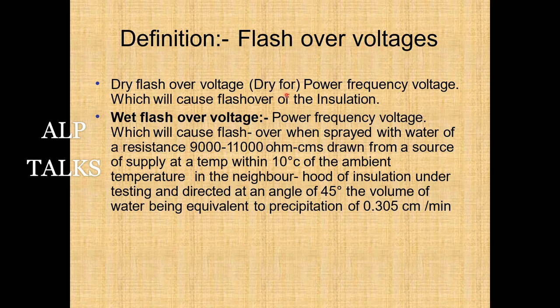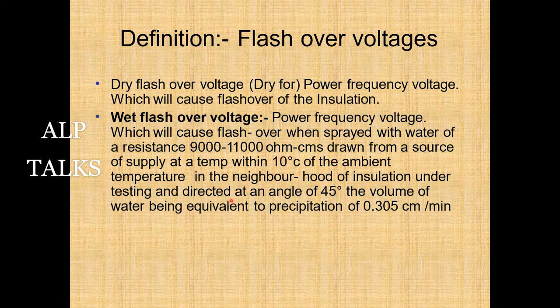Dry flashover voltage is the power frequency voltage which will cause flashover of the insulation. Wet flashover voltage is the power frequency voltage which causes flashover when the insulation is sprayed with water of resistance 9,000 to 11,000 ohm-centimeters, drawn from a supply at a temperature within 10°C of ambient temperature, directed at 45 degrees, with a volume equivalent to precipitation of 0.305 cm per minute.